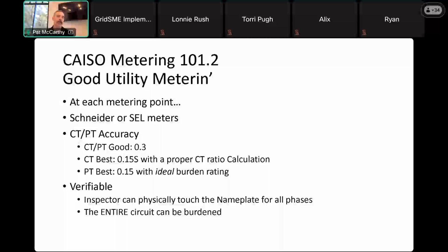I'm going to talk a little bit about that because it's an often overlooked design consideration. A current transformer is sized for a certain amount of current. Let's just say 1,000 amps. If it's a normal class current transformer, a 1,000 amp CT, it's good from 100 amps through whatever the rating factor is. Let's say the rating factor is 2, so it's good from 100 amps to 2,000 amps.